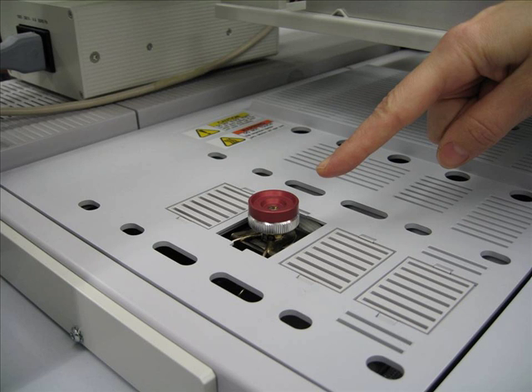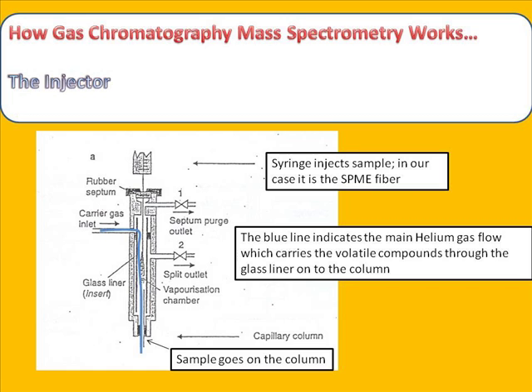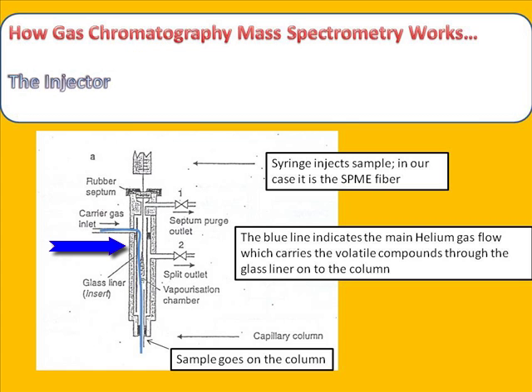Here you can actually see the top of the injector again. Here is a schematic of the entire injector port. The sample is evaporated into the hot glass liner, as you can see here, and is then carried with the helium gas, shown here with the blue line, onto the column.